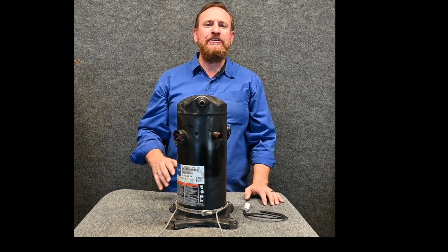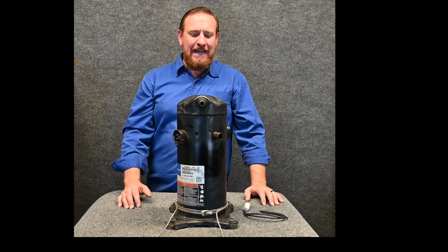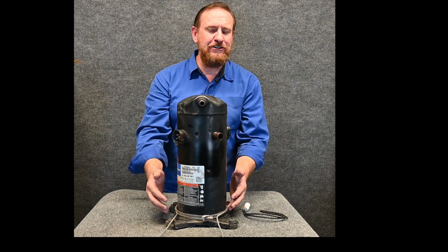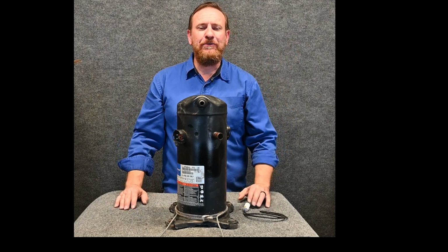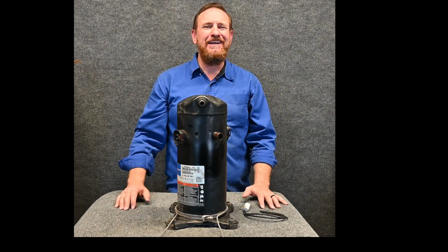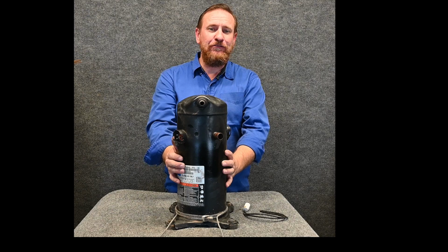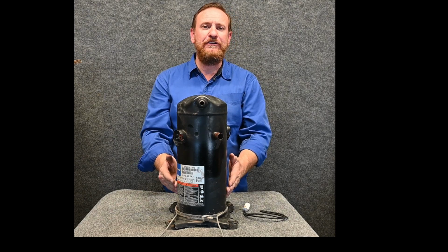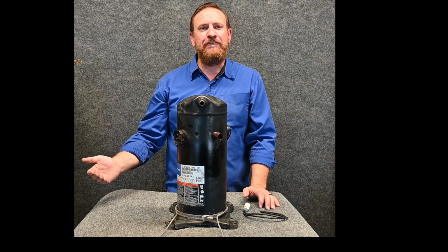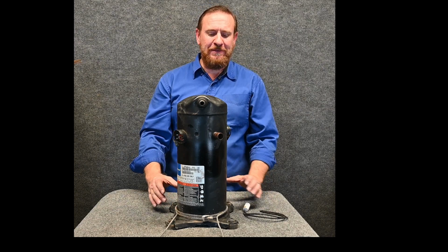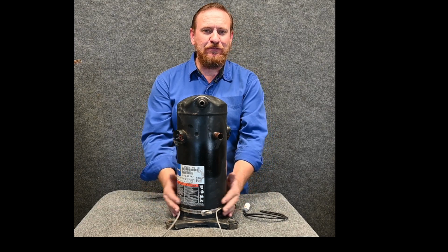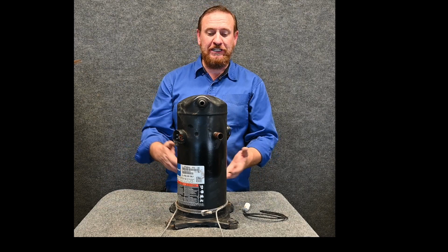this oil. When I was a younger tech and I was working in Florida, I would see these shorted out all the time, and I would just cut them loose and be like, hey, you don't need to worry about that. And I thought I was saving the customer money. But really I was putting their compressor at risk, because even though it wasn't working at a low temperature, it's still possible for that refrigerant wanting to migrate to the oil.